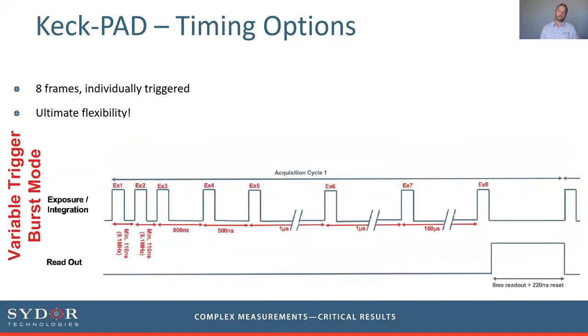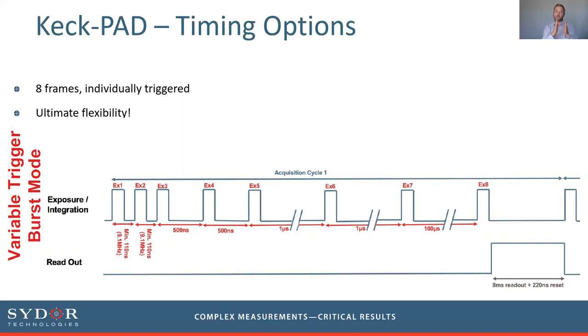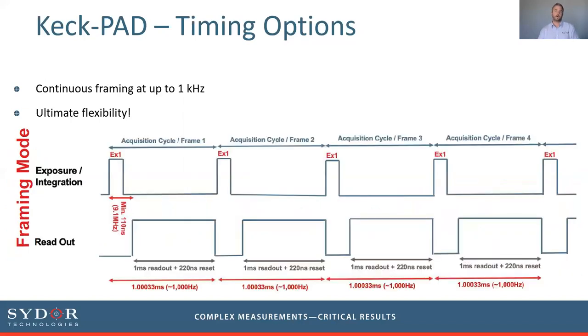Another application is to use those eight frames but spread out their timing to elongate the total image acquisition time. For something like catalysis, where very fast things happen at the start of a reaction, you could burst the first two or three frames very quickly, and then let the interframe time between subsequent exposures decay in a logarithmic fashion through to the eighth exposure before reading out again.